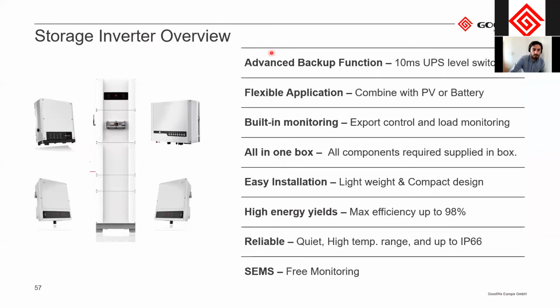So as a quick overview, it's the integrated advanced backup function. Also, if I didn't mention it, it has a 10 millisecond UPS level switching. It doesn't mean that it's a UPS system, but the switching time from on-grid to off-grid, in case the grid is disconnected, the switching to the backup loads is within 10 milliseconds. This means that you won't even notice it. The frequency of the grid is 50 Hertz, that's 20 milliseconds. So with a switching time of 10 milliseconds, it's uninterrupted, so to say.